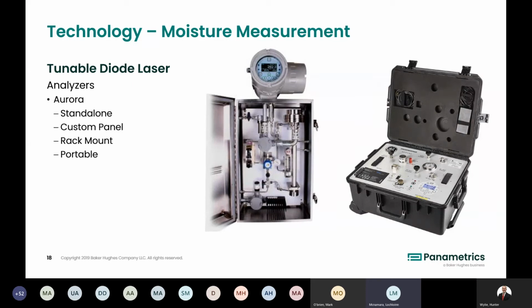What that generally relates to is that something from the process may have broken through the sample system or the filter to the mirror that is located at the base there. Under normal circumstances, that mirror should be kept very clean and highly polished, because the signal path is quite defined from the laser back to the photodiode. The Aurora is able to handle some attenuation from a dirty mirror, but eventually there may be some oils or contaminants that have hit the mirror, so you'll get a warning on the screen saying weak signal error, please check mirror.